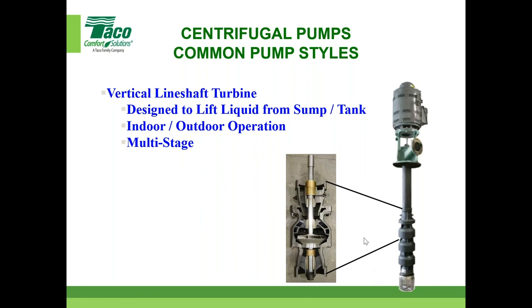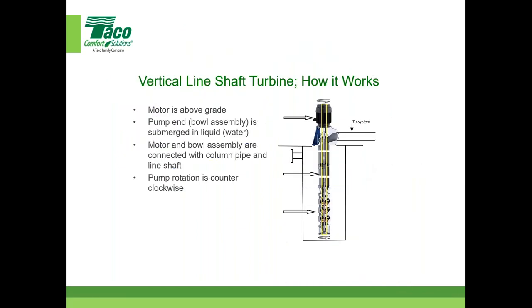For HVAC, it's probably condenser water, although we are seeing some folks think about, in a mechanical room, maybe saving even more space if space is that much of a premium and installing one of these, but they would need some type of sump to work in the design of the system. So, but nonetheless, they need to go in a sump of some sort, vertical line shaft turbines, and they all have their own different terminologies. Like we all consider this the motor. In their thought process, it's the driver. So it's a synonymous name. So something to consider. Just so you can see how it works.